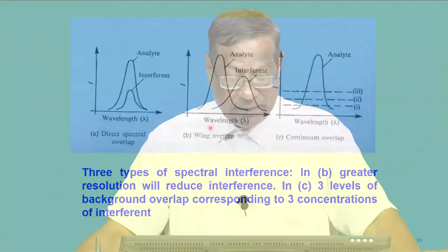So, here I am showing you some of the spectral interferences. You can see part A, here the interferent is there, analyte is here above, but you are supposed to subtract the interferent, this much of emission has to be subtracted from the total area of the analyte. Here the interferent is totally inside the emission spectrum. So, this is known as direct spectral overlap, and if you see the middle one, a small portion of the interferent is accounted by the detector, most of it is not accounted by the detector. So, I should be able to correct, this is known as wing overlap, and the next one is continuum overlap.